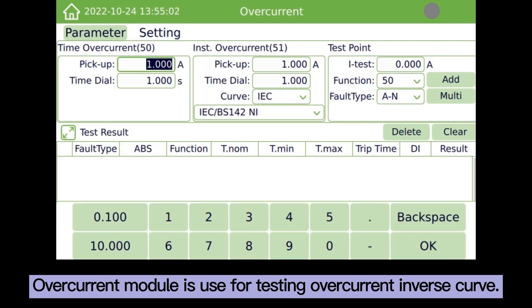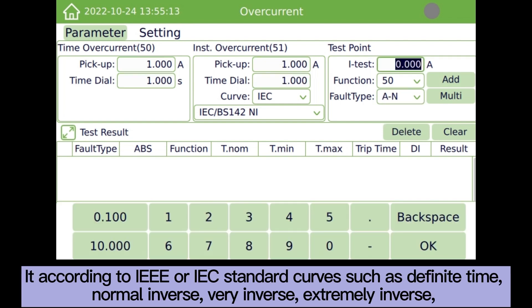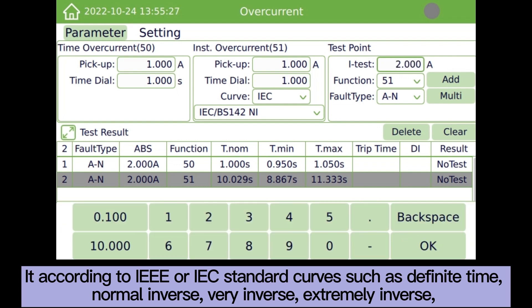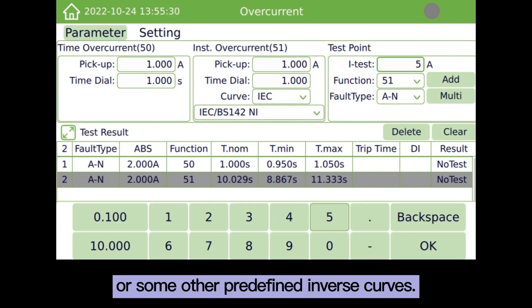Overcurrent module is used for testing overcurrent inverse curve. It according to IEEE or IEC standard curves such as definite time, normal inverse, very inverse, extremely inverse, or some other predefined inverse curves.